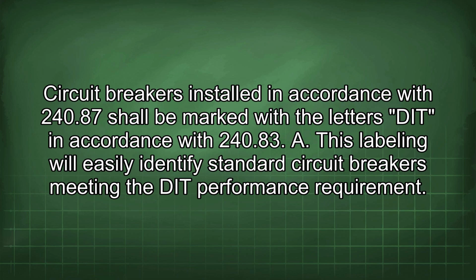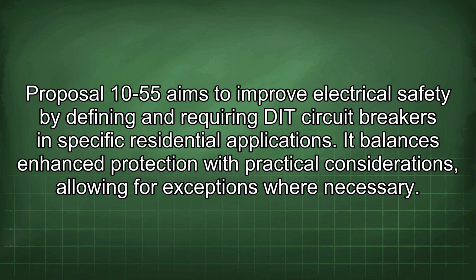Circuit breakers installed in accordance with 240.87 shall be marked with the letters DIT in accordance with 240.83(A). This labeling will easily identify standard circuit breakers meeting the DIT performance requirement. Proposal 10-55 aims to improve electrical safety by defining and requiring DIT circuit breakers in specific residential applications. It balances enhanced protection with practical considerations, allowing for exceptions where necessary.